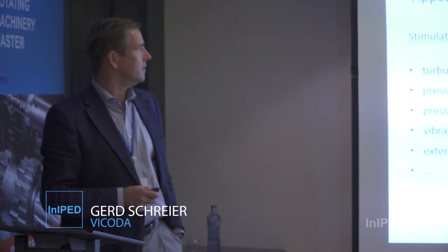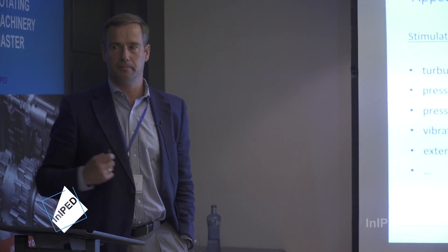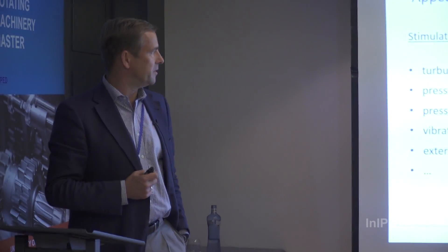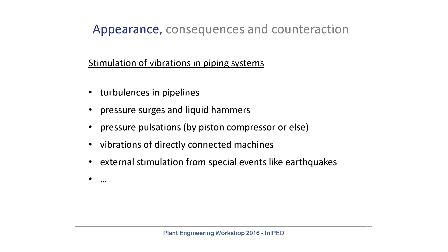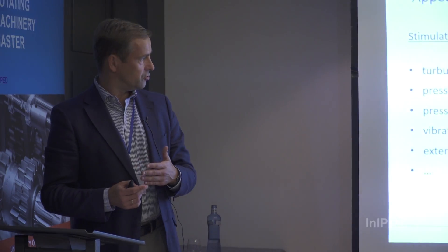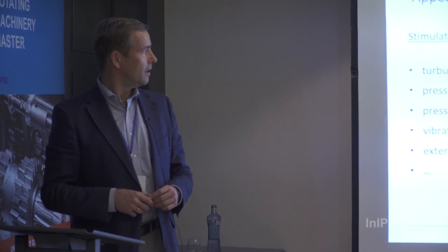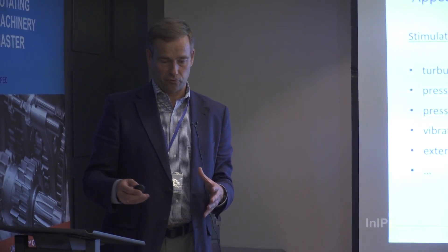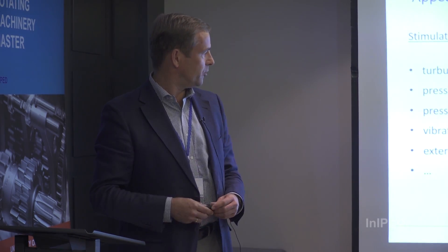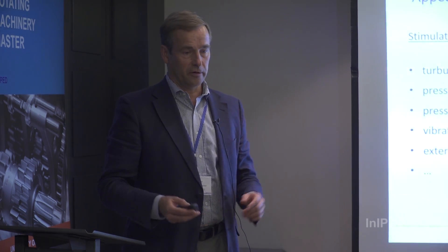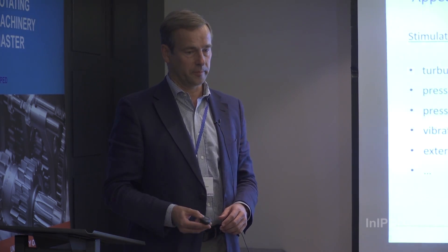If you excite a piping system — and it can be done very easily — what usually excites it is either turbulences on the pipeline, pressure surges if you open or close a valve, or a pump pushing fluid or sludge through the pipe system with a certain frequency. Vibrations can also come from a pump directly connected to the pipe system mechanically, or from external stimulation such as an earthquake or wind.